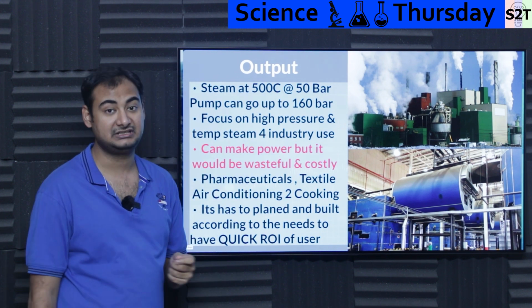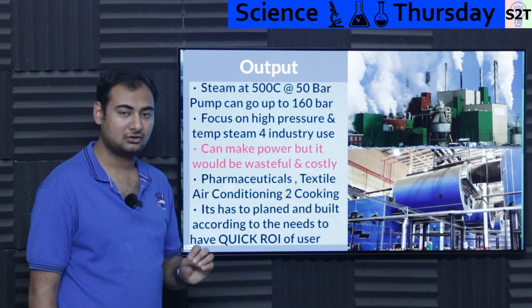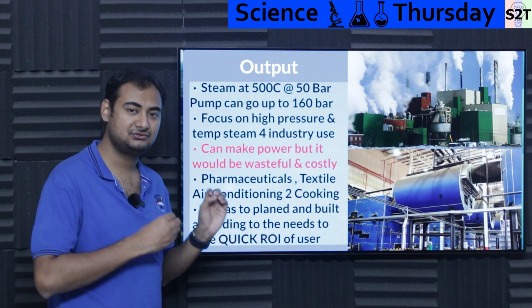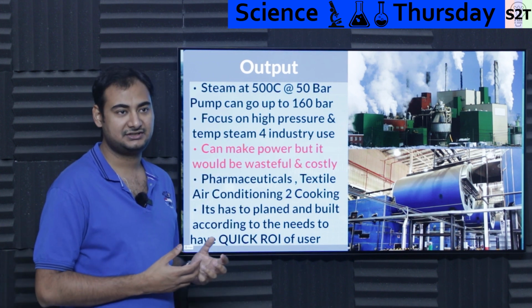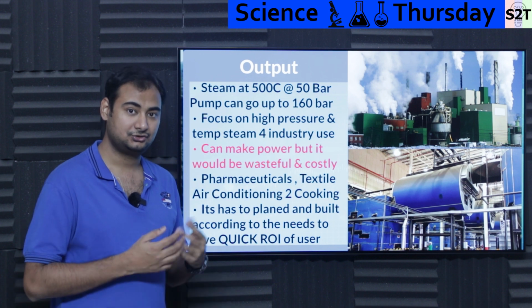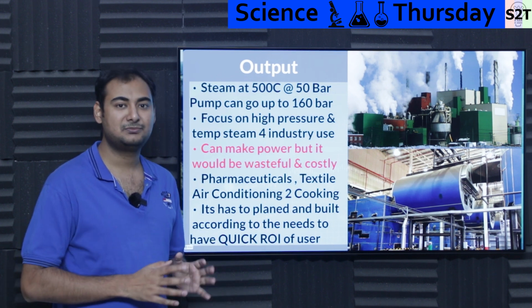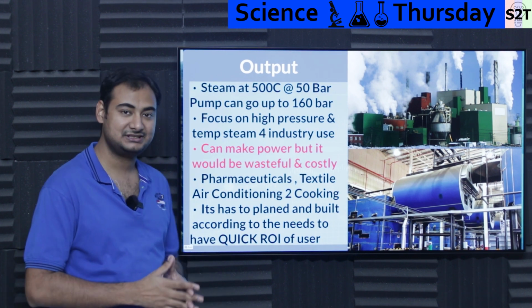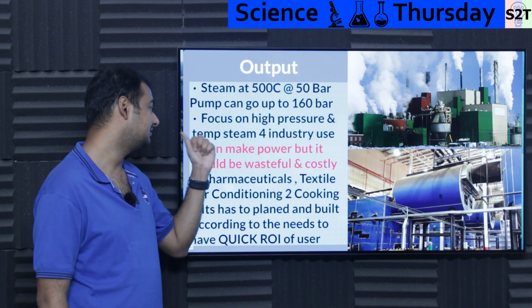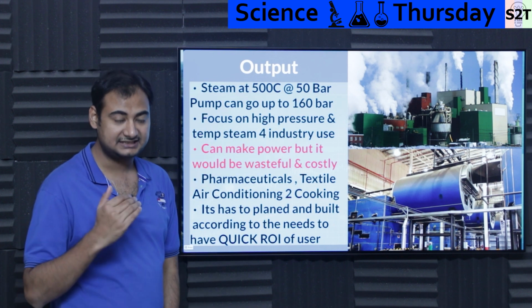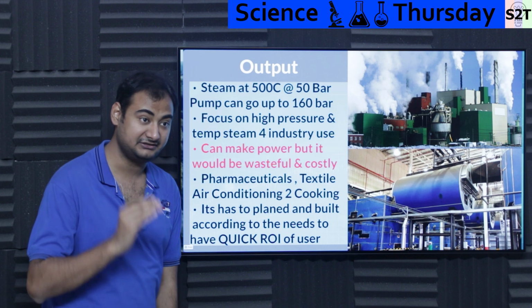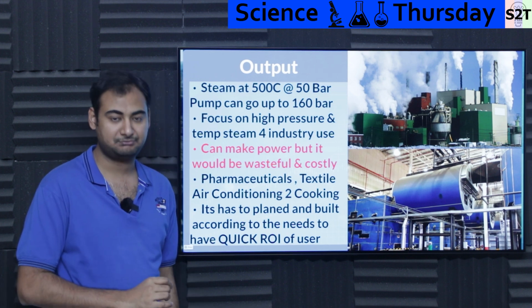So the core focus is on high pressure and temperature steam for industrial use — they're not focusing on power generation. Can you use this steam for power production? Yes. Should you do that? Hell no, because you'll go bankrupt if you try. So it's one of those things where you need high pressure steam, and that's the whole point — high pressure and high temperature steam. If that's your requirement, only then does this puppy make sense.